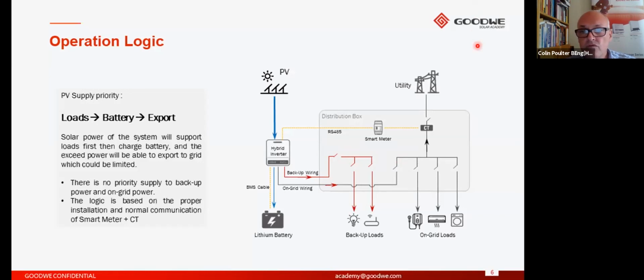If we continue to look at this, we have an RS485 connection to our device called the smart meter. This device intelligently controls the need for charging or discharging the batteries. This smart meter is connected to a CT, which has to be placed between the incoming point of the building and the supply from the grid.